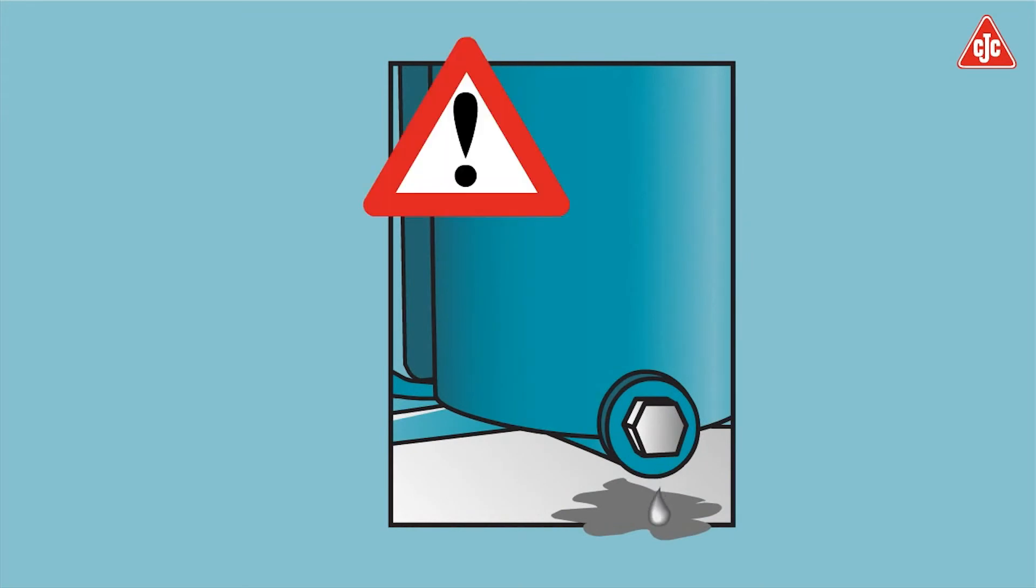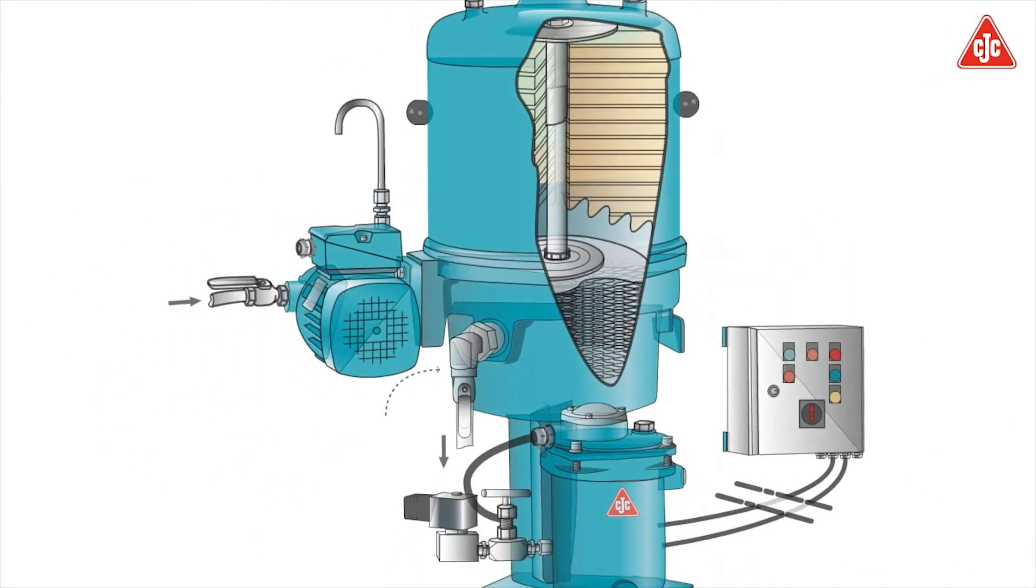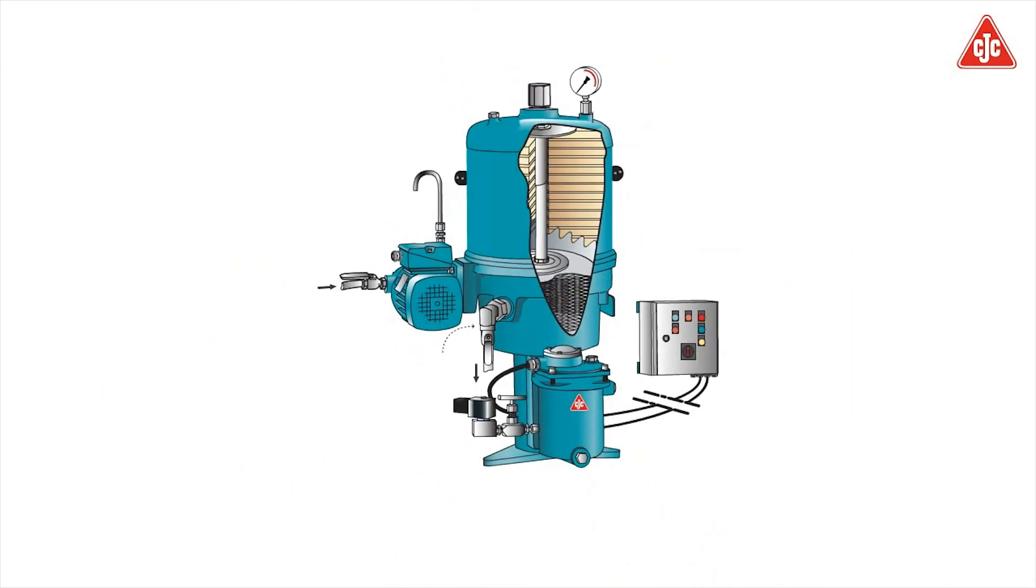Be aware that oil spillage is a serious safety risk. Keep clean. And again, remember that the filter inserts must be replaced at least once a year or at a pressure drop of 2 bar.